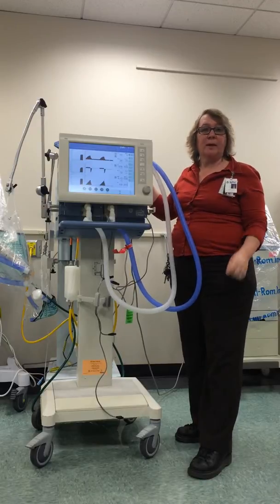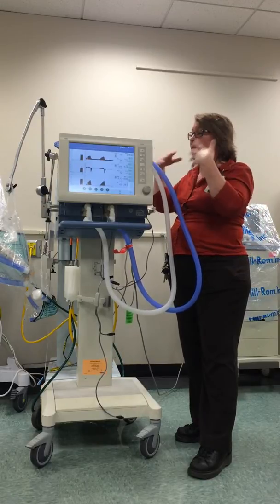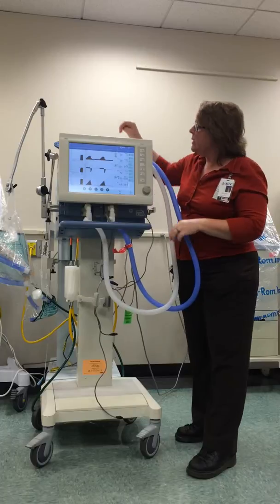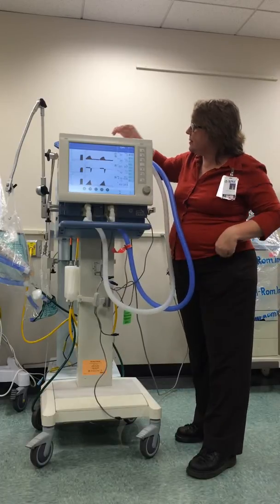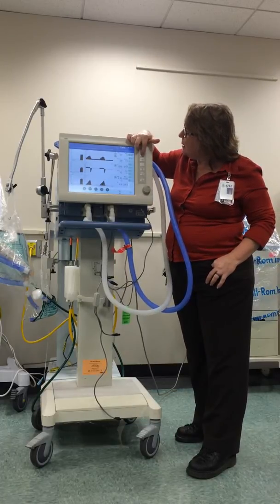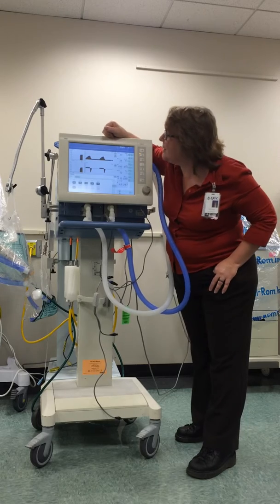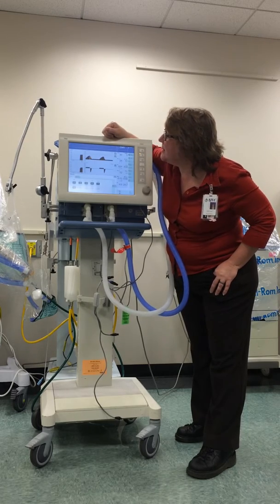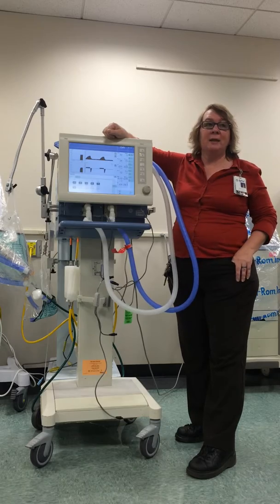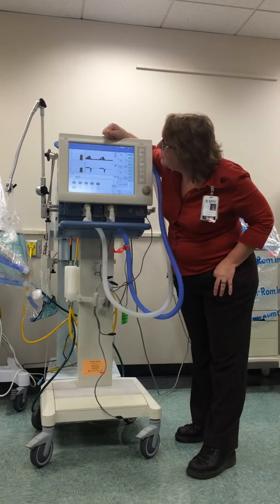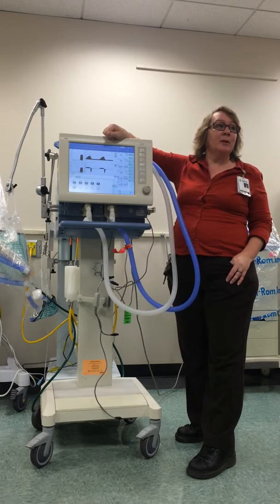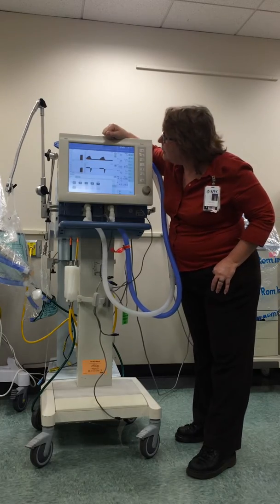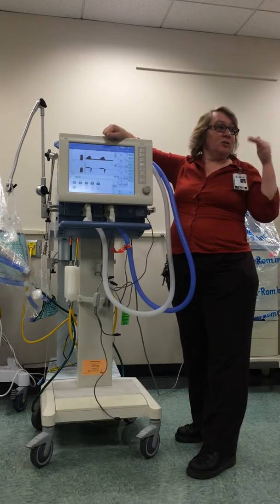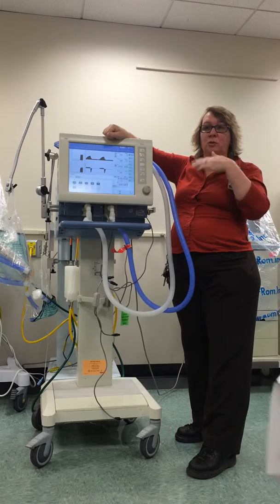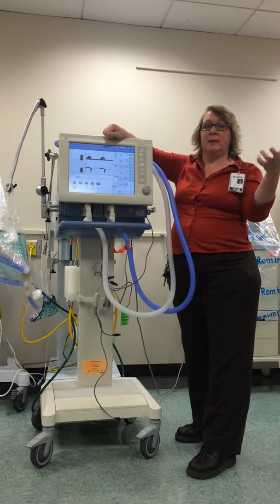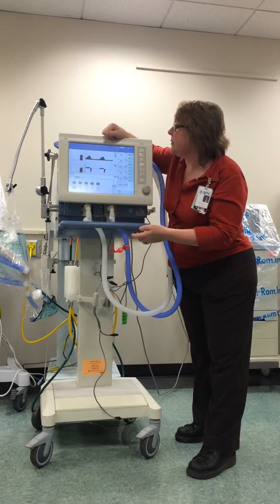They're not made to run them. They can't. There's too much work involved inside of the ventilator. So it's only there for emergency purposes. Alarm limits. So on this one, MV, I can set my high minute ventilation and my low minute ventilation. PAW is my high pressure limit. I can't set a low, it automatically defaults to 1, so you can't change it. Remember I told you you only set what you can set, and you'll learn where they need to be set. I'm just telling you what's here.